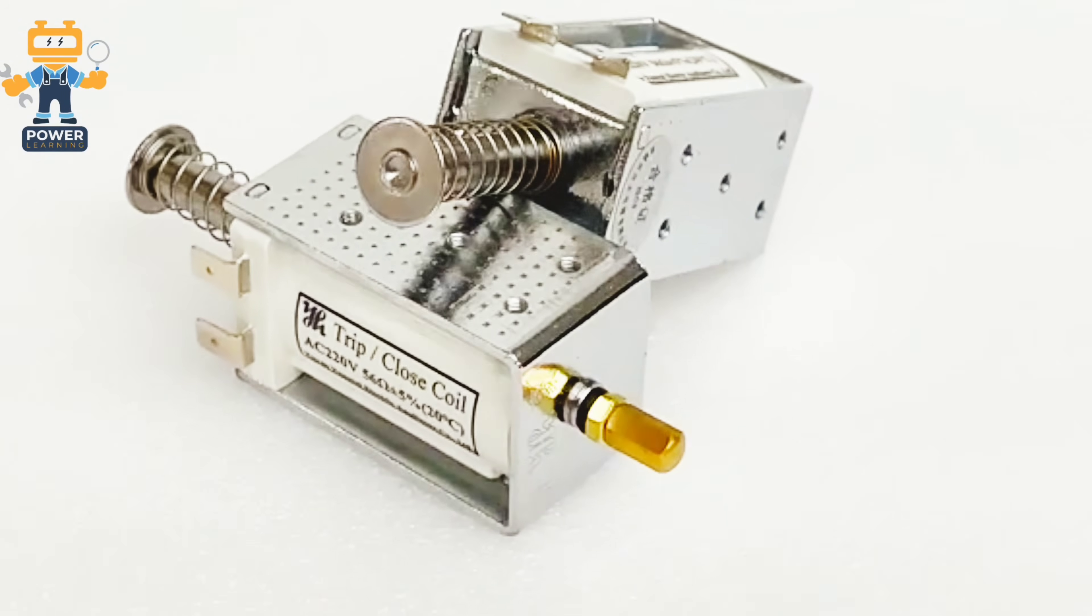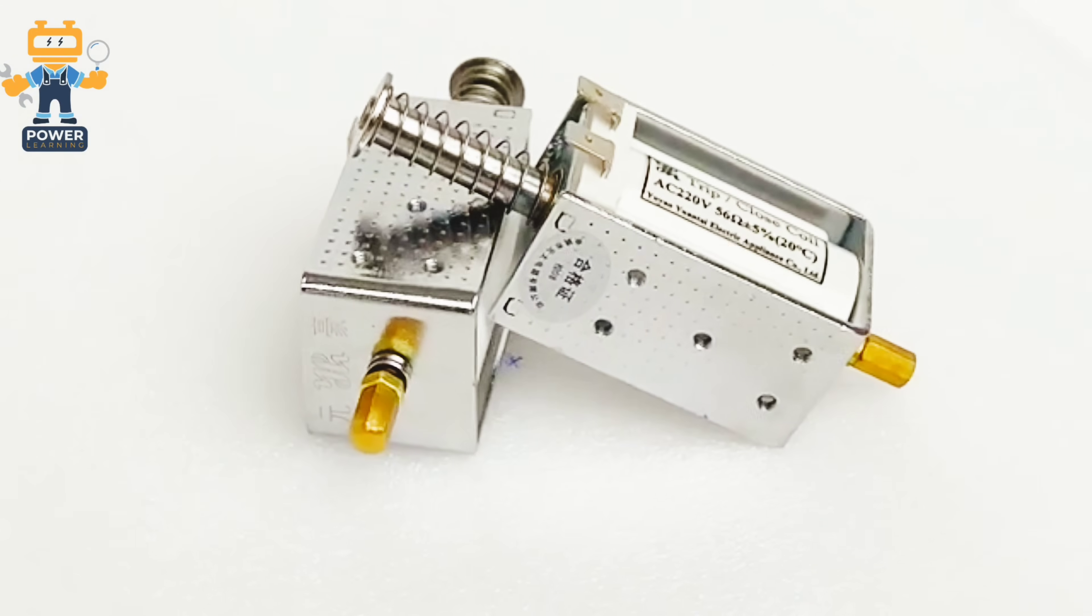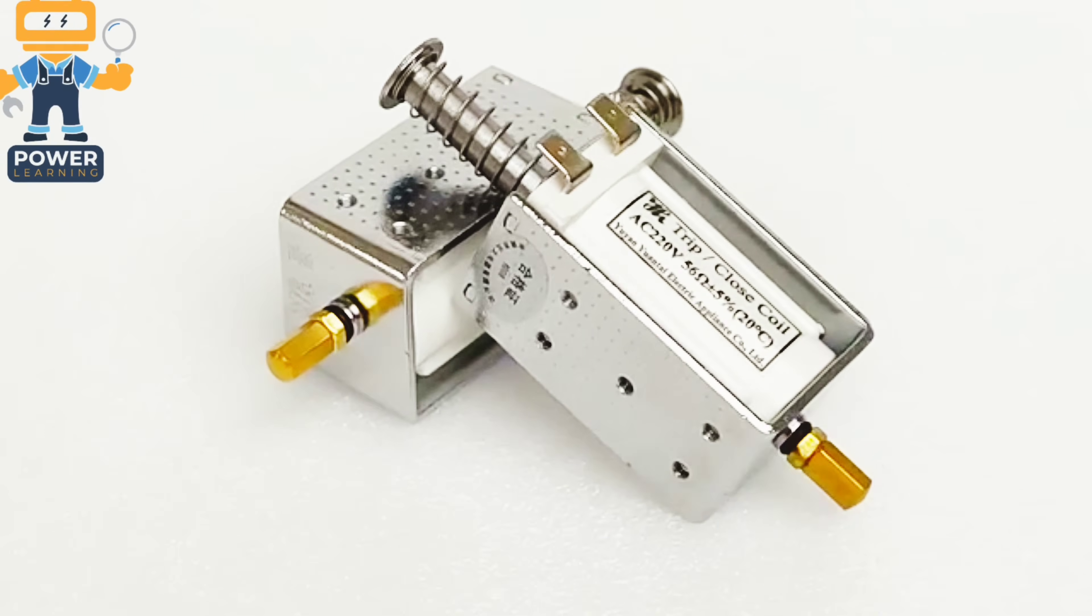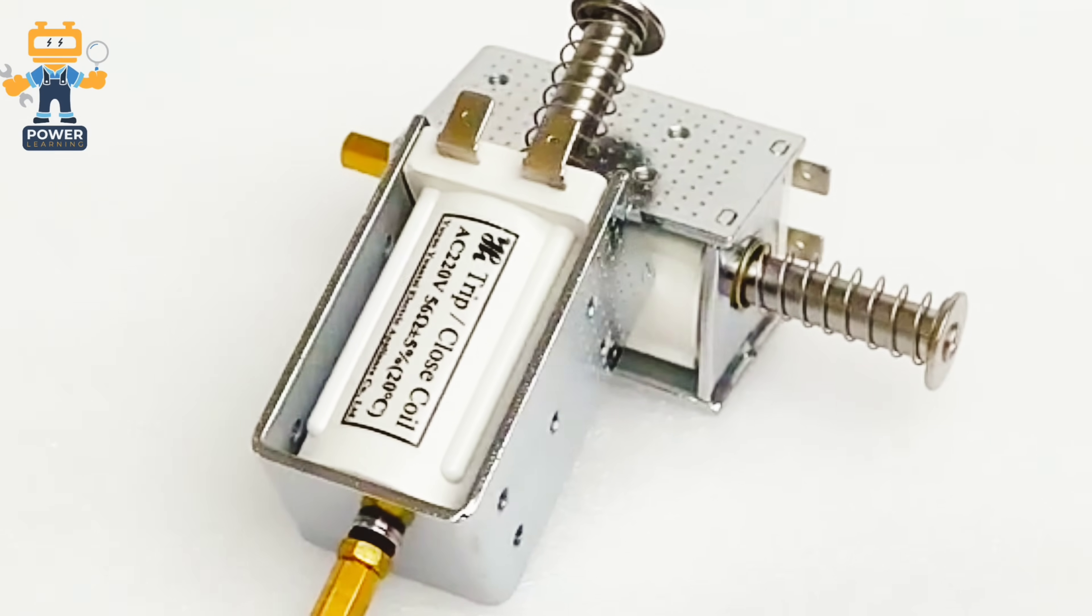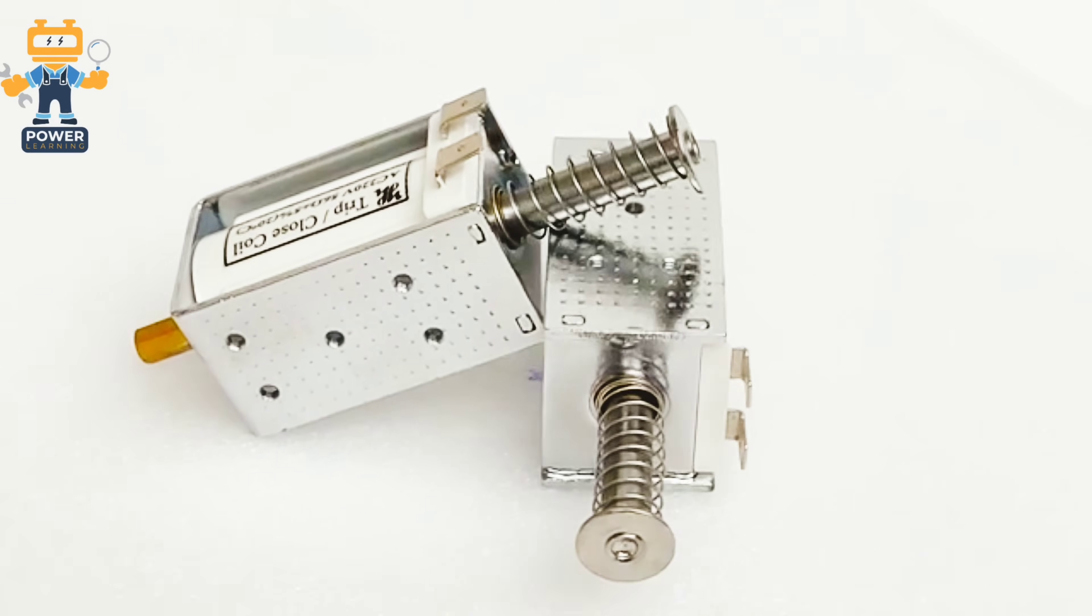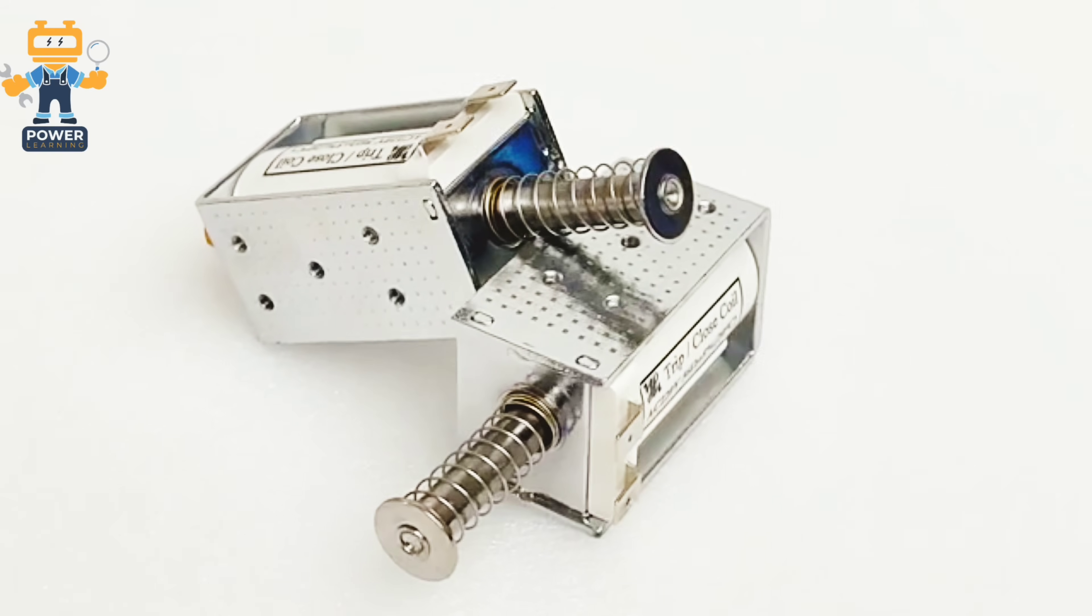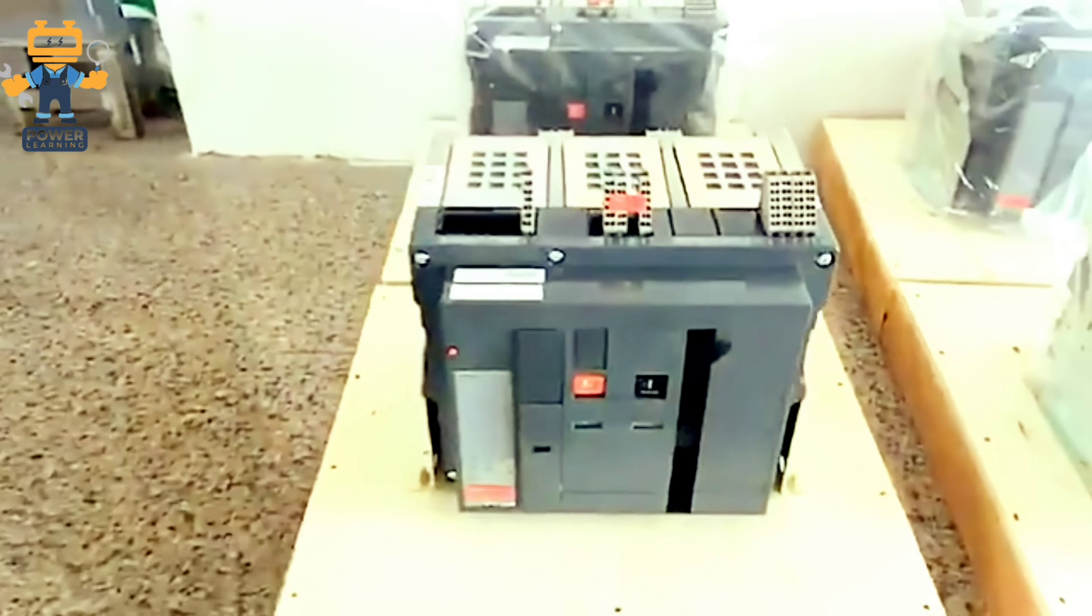So now in front of you, these are trip coils. These coils are very important for the breaker. Without this coil you cannot operate the breaker automatically. These coils we are using to turn on and turn off the breaker. These coils are called shunt opening and shunt closing coils. Normally in these coils we have different ratings like 220 volt, 12 volt, 24 volt AC DC.